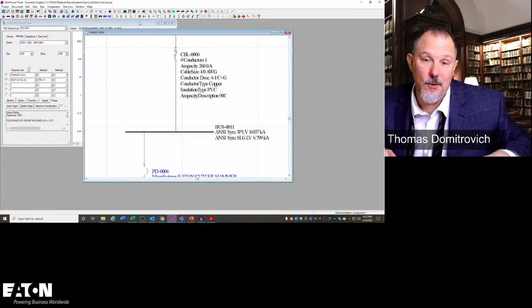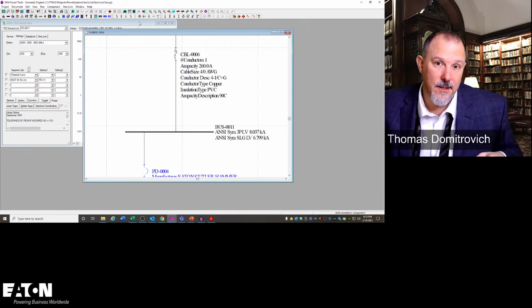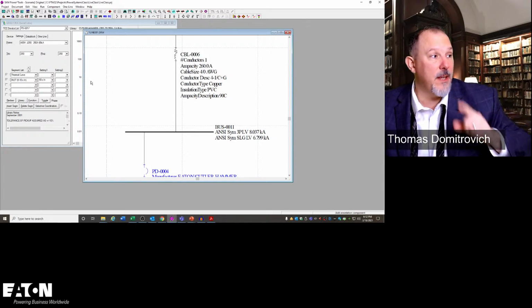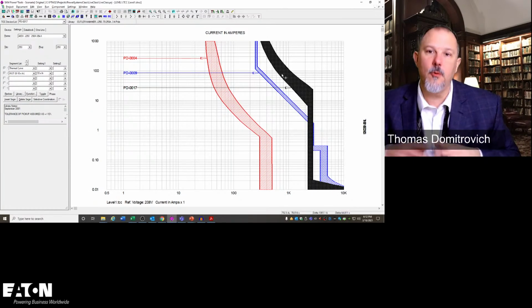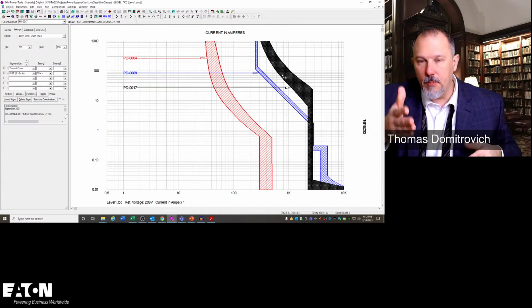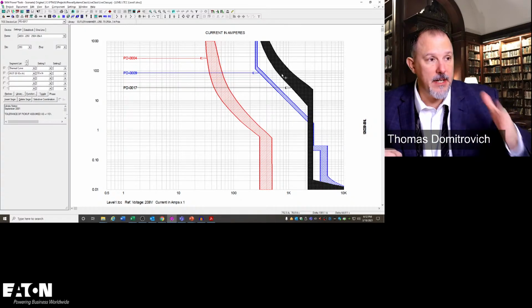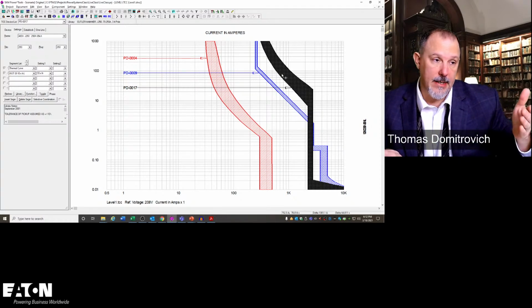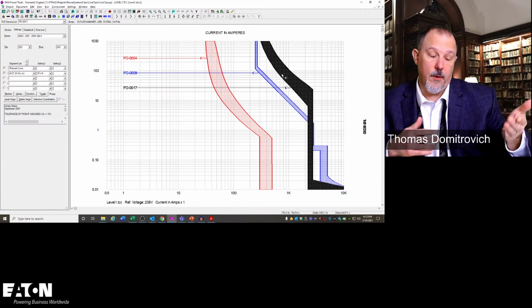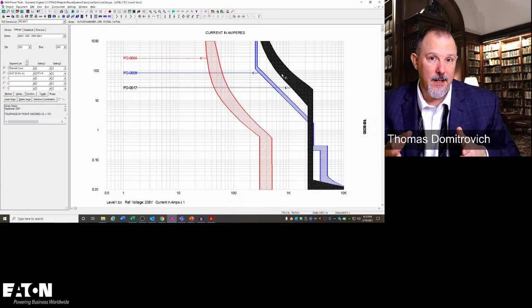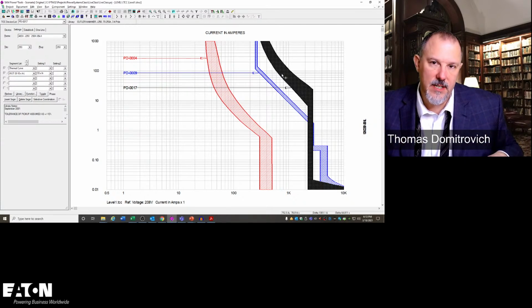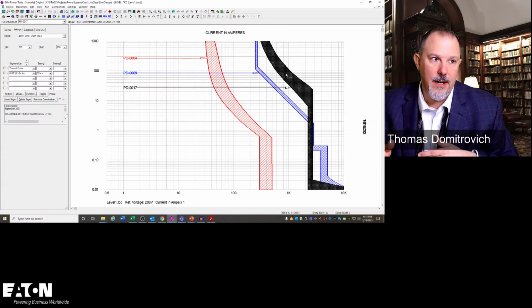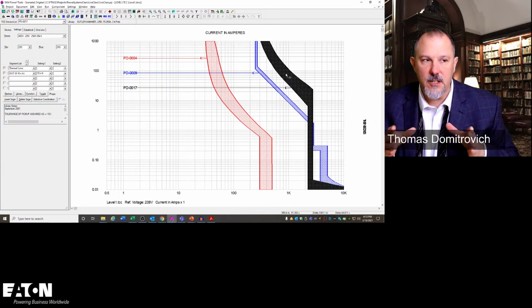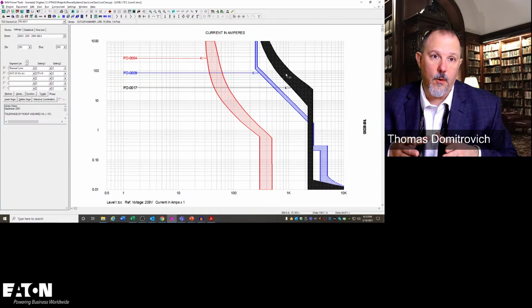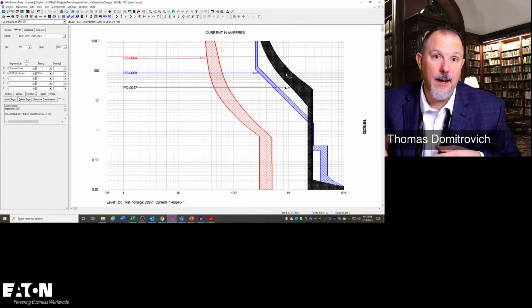So I'd sit down in the healthcare world and say, look, you're ignoring your ground fault current, which I know for a fact, because of testing, is going to trip that thermomagnetic circuit breaker. So picture yourself as an engineer on the stand. Somebody gets hurt, somebody gets killed, and they say, well, we had a cascading event. Did you know? Well, yes, I did. Well, the code only requires this. That's the minimum requirement, but do you know better? Yes, I do. So it puts you in a sticky wicket. I think 0.1 seconds puts a professional engineer in a sticky wicket. You can fall back on saying 0.1 seconds is all I need to do, but the moment you have a cascading event, especially one that causes a loss of life or hurts somebody, you're into a sticky wicket. The other sticky wicket is that I've added delays and increased incident energy.